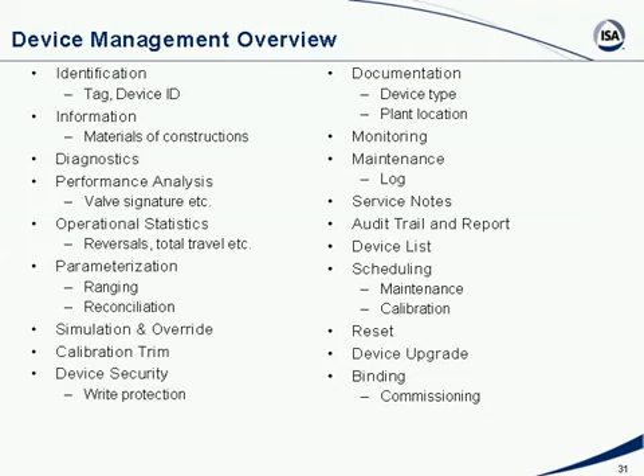General information such as materials of construction, let's say my pressure transmitter, what diaphragm material, is it stainless steel, Hastelloy, or tantalum, what flange materials do I have, what is the process connection, and all of that information is of course useful if I need to replace a device, let's say. Then I can easily get a new device, because whatever information is available inside the device is always much more up to date than the information that I might have on some document stashed away in a drawer somewhere.